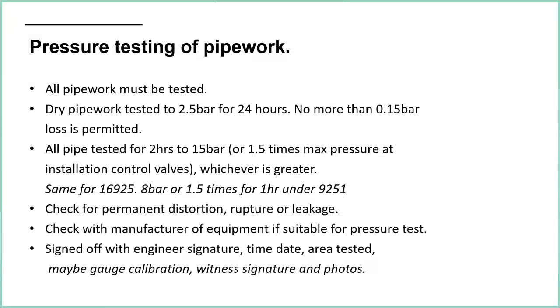I know from Project Fire, obviously we're the manufacturers of our Zone Check product, that the maximum working pressure is 12 bar for that. So we're not saying that it won't do a pressure test for 1.5 times, because absolutely that was part of the approval, that it could be tested up to that. So again, working pressure and hydrostatic pressure are two different things. We certainly do not recommend that the pump on the Zone Check, not the fire pump I'm talking about, be run at higher than 12 bar. But it's absolutely fine to be testing it above, to the hydrostatic test.